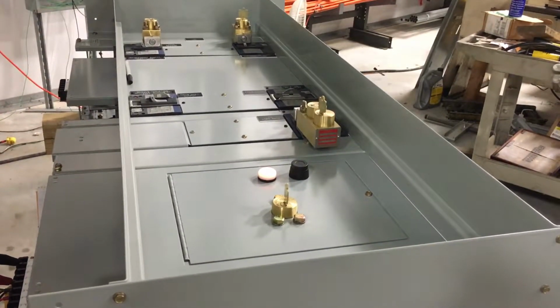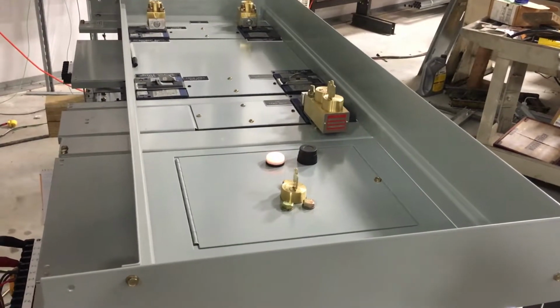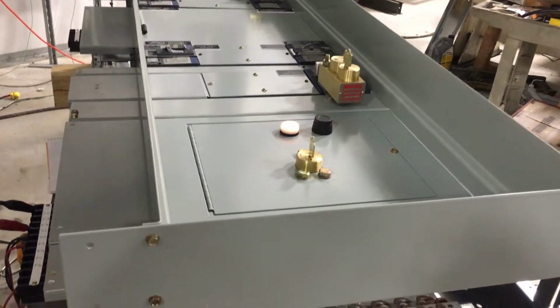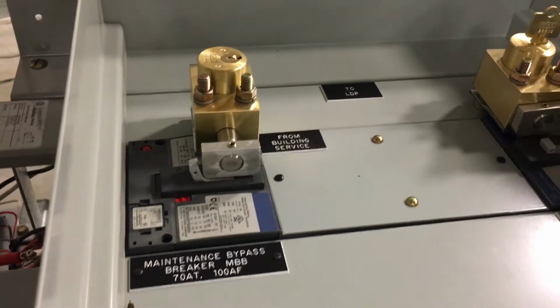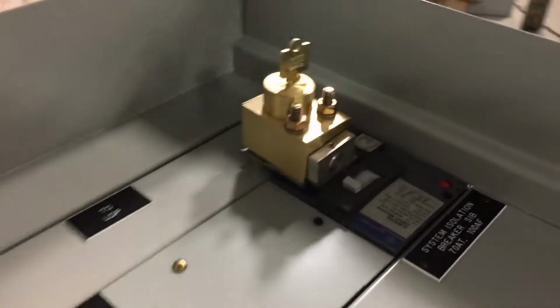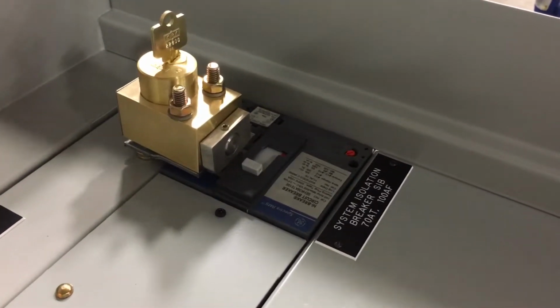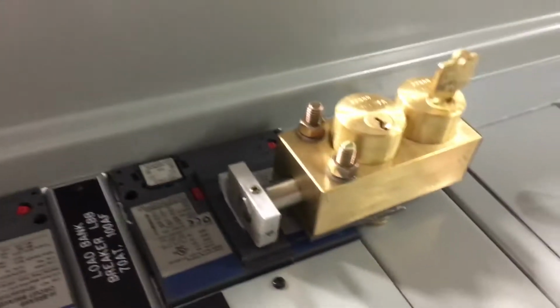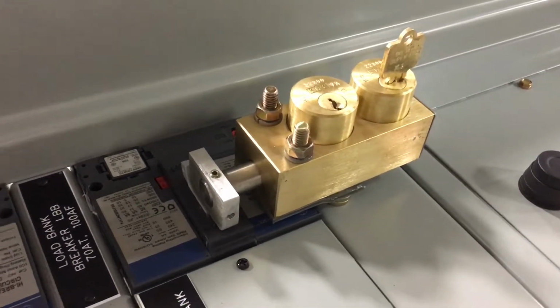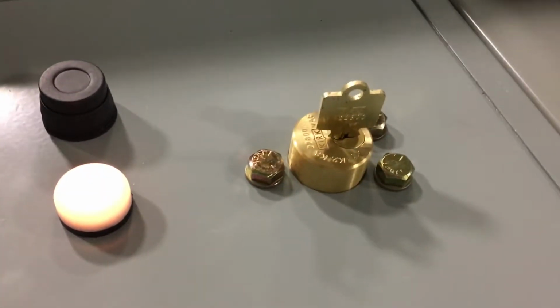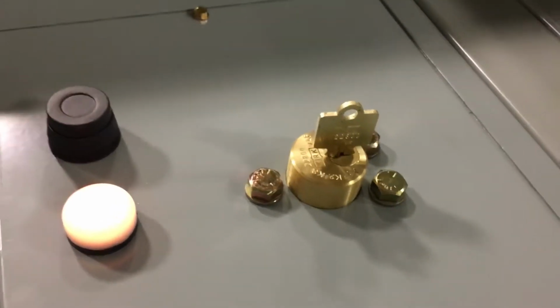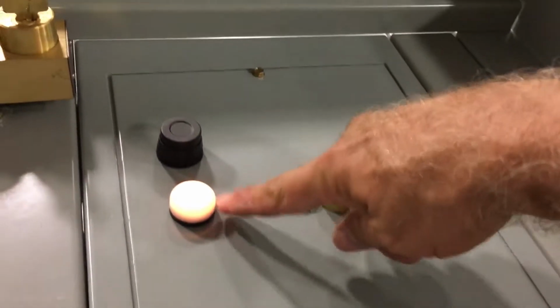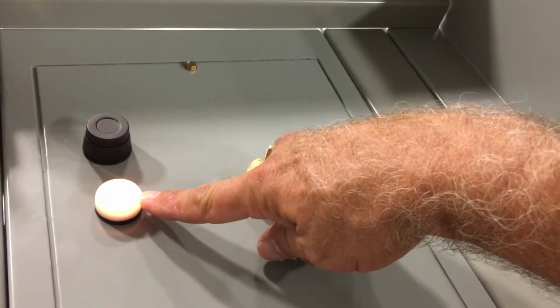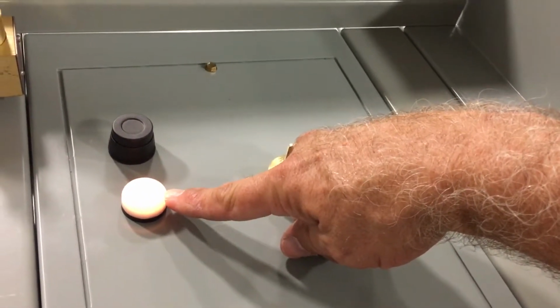Testing the Kirk key interlock scheme on a maintenance bypass panel with load bank testing. Initially, breaker MBB is locked open, SIB is closed, load bank breaker is locked open, key K2 for the MBB is locked in the SKRU. The light's on, showing that the UPS system is in maintenance bypass mode.